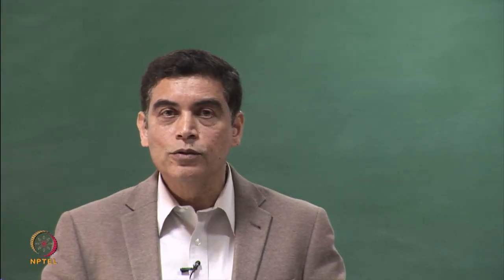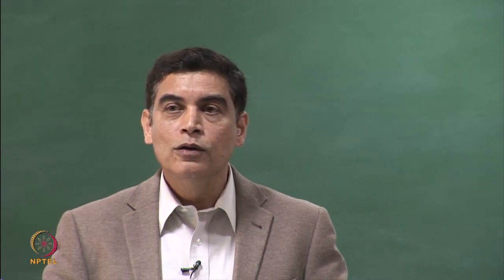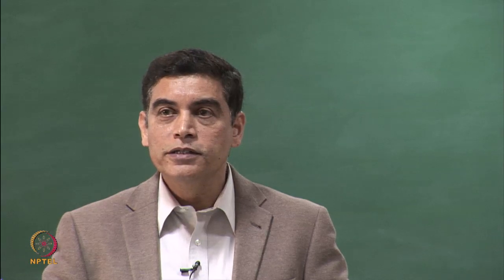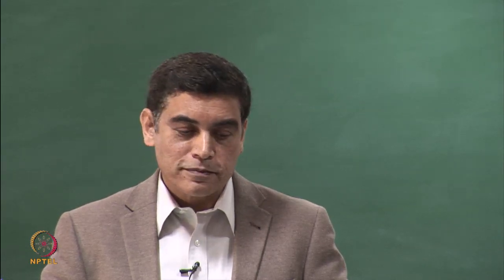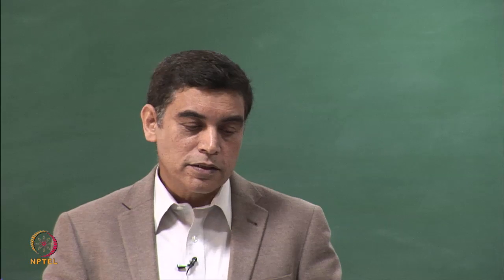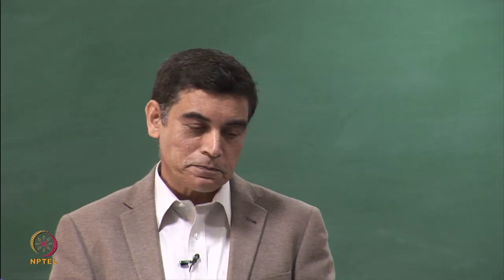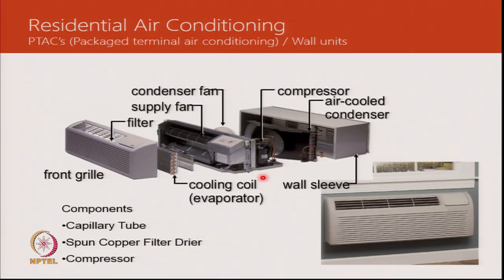The key concerns there are totally different from heat transfer. So you want low noise, you want ability to adjust speeds, and a certain resistance to carryover of refrigerant droplets. Then in addition to that, there would be factors related to aesthetics. The bare coil by itself would not look very elegant, so we need to cover it up, and you need to have some means of having access to the filter, because that would need more frequent cleaning. So from design and selection of an evaporator coil, we would end up looking at the full gamut of components which would be needed.